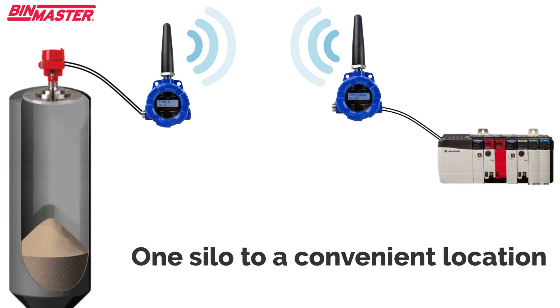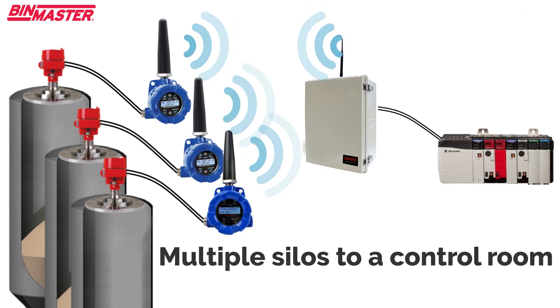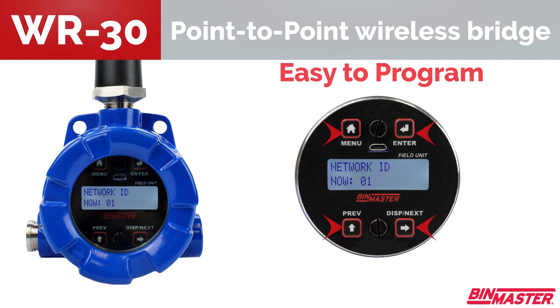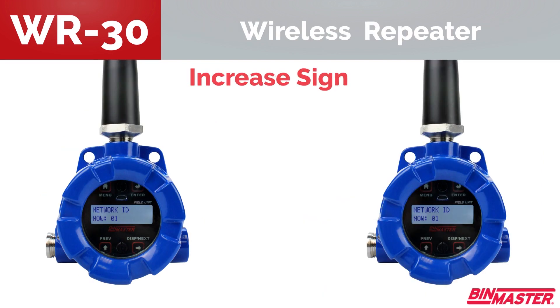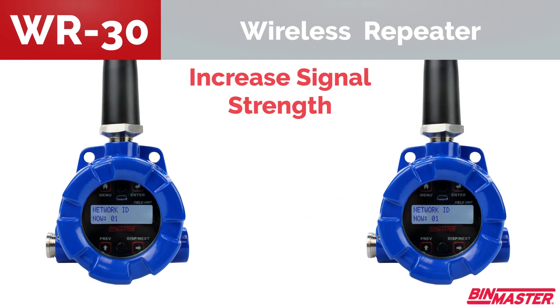The wireless modules work by taking the sensor output — whether it's 4-to-20, Modbus, or a contact — and converting that into a 900 megahertz signal, sending it wirelessly back to a base station in a point-to-multipoint configuration. You can also have a point-to-point relay system. The 900 megahertz technology can communicate up to one mile outdoors or a half mile indoors and is very robust and rugged. We also have repeaters so if something is in the way — a tree or a building — you can use a repeater to route the data around the obstacle.